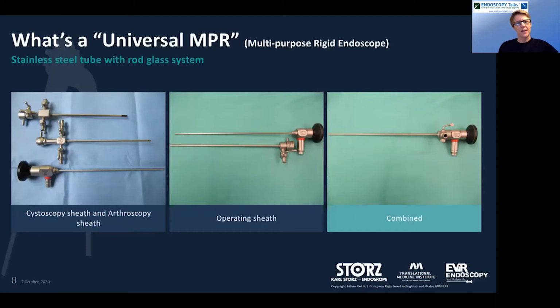And oftentimes we'll have a variety of different sheaths to protect that endoscope. So whenever you're using a rigid endoscope, you must always use a sheath. And there's a variety of different sheaths available. So you can have a cystoscopy sheath, an arthroscopy sheath, but really the basic principle of a multi-purpose rigid endoscope is using this tube inside a cavity.